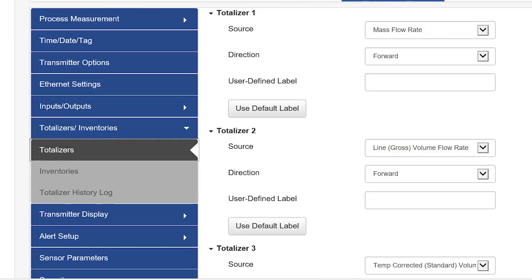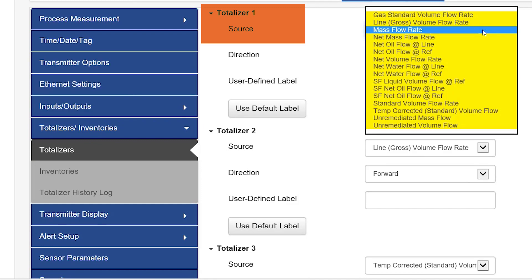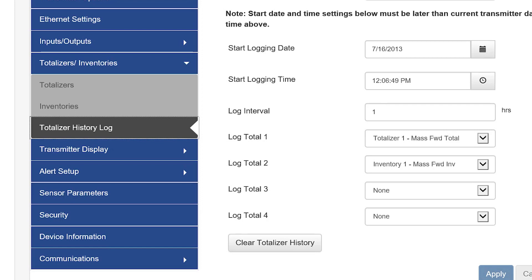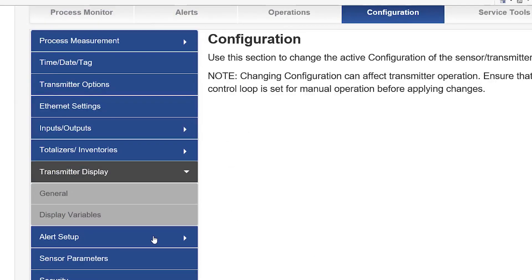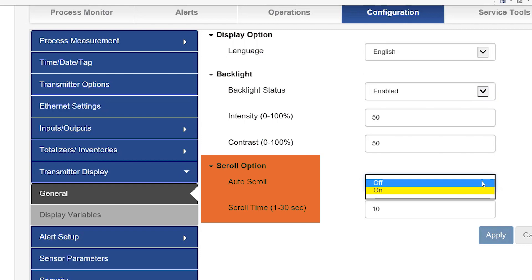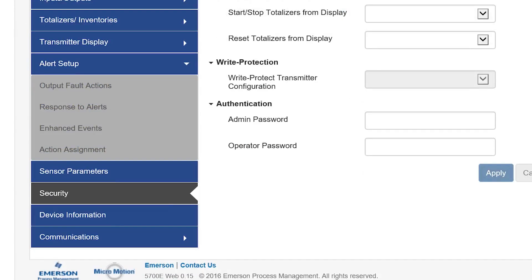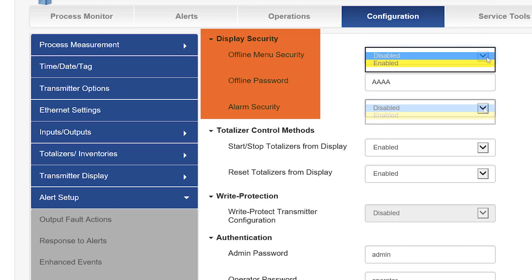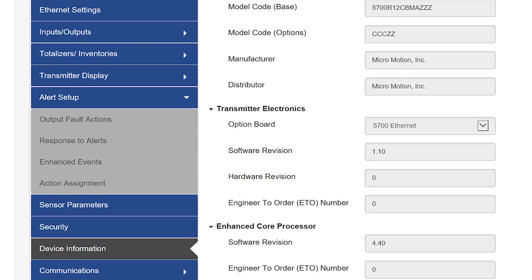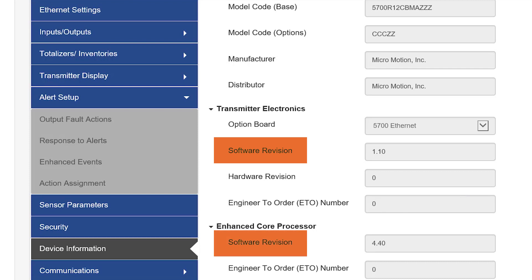The totalizer and inventories menu allow the user to configure totalizer source and flow direction. Totalizer history log allows the user to select the totalizers to be logged, along with the date and time, and there is also the option to clear totalizer history. The transmitter display menu allows the user to configure the transmitter language, backlight, and auto scroll option. The security menu allows the user to issue a password for offline and alarm security, along with assigning the passwords for the admin and operator users. The device information menu shows the software revision for the transmitter and the core processor, along with the licensed features.